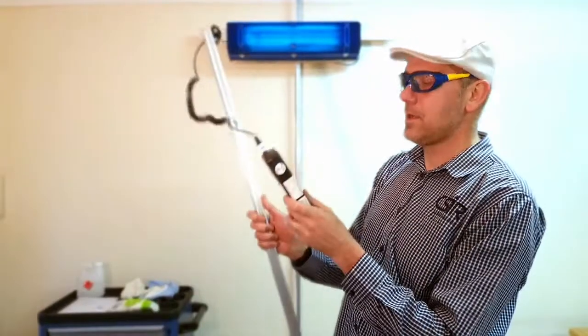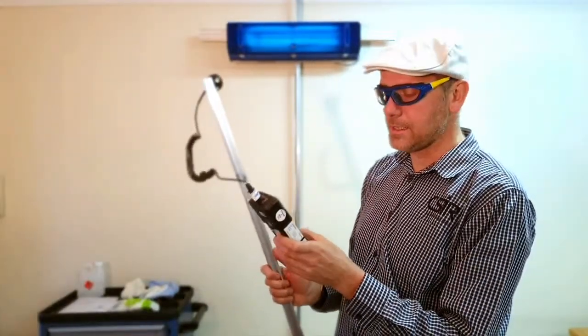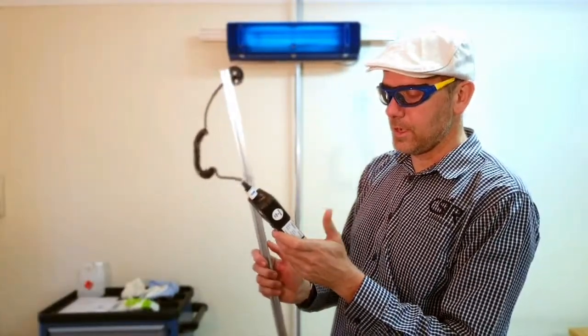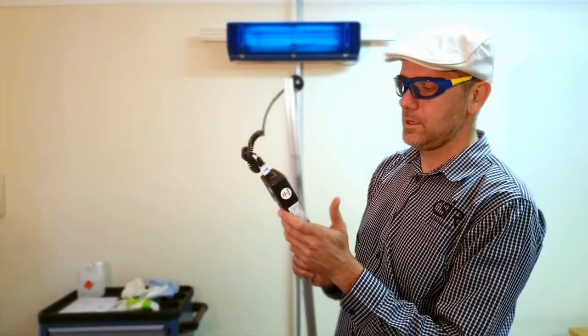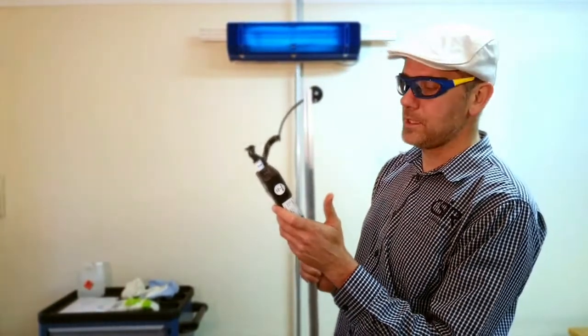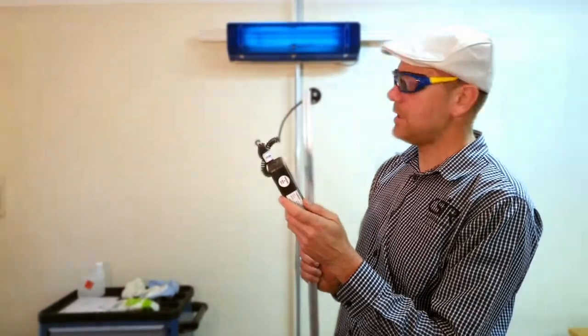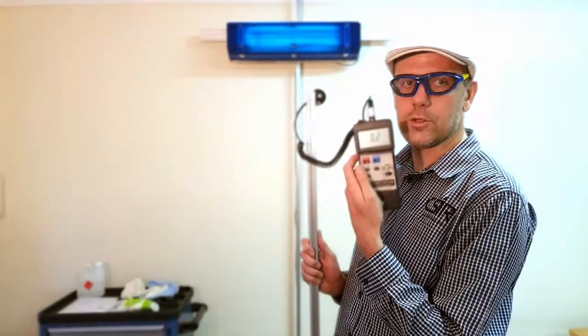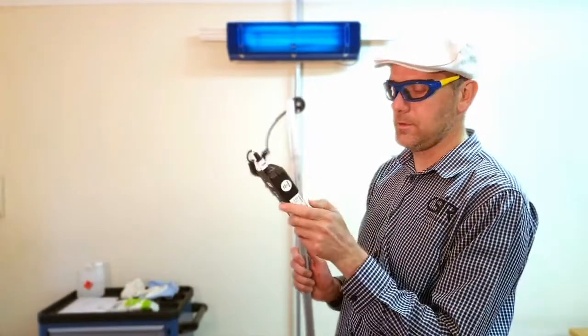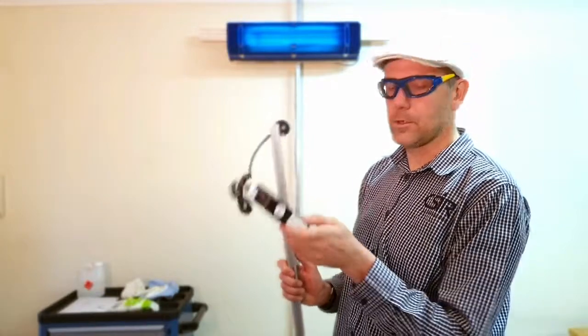We can take that. We want to take a lower room eye safety reading. We put the radiometer into that range and take that measurement at 1.7 meters, and we're still at about 0.2 microwatts, so it's still safe. Good, our work here is done.